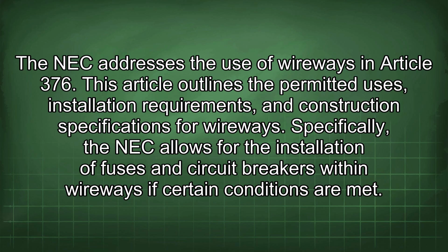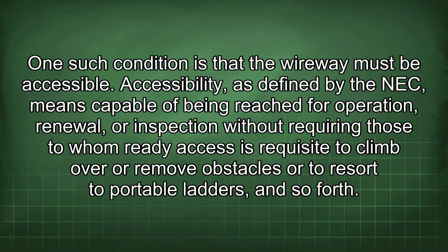The NEC addresses the use of wireways in Article 376. This article outlines the permitted uses, installation requirements, and construction specifications for wireways. Specifically, the NEC allows for the installation of fuses and circuit breakers within wireways if certain conditions are met. One such condition is that the wireway must be accessible.